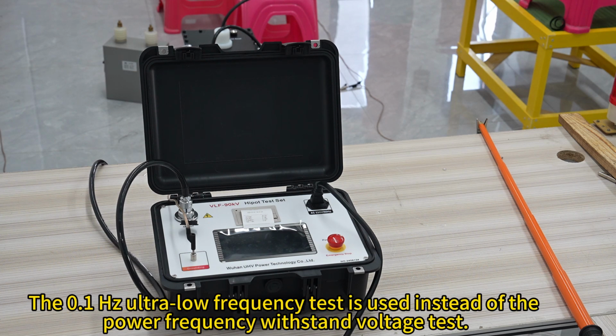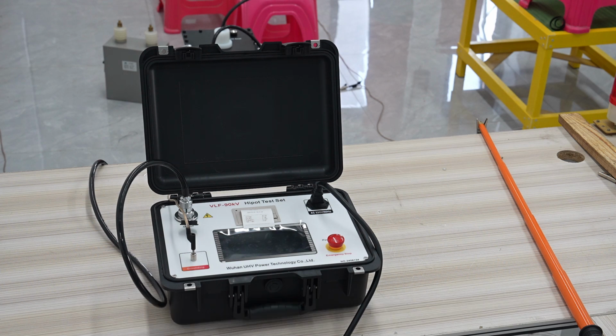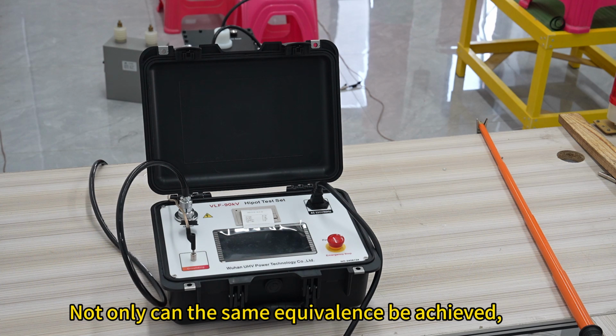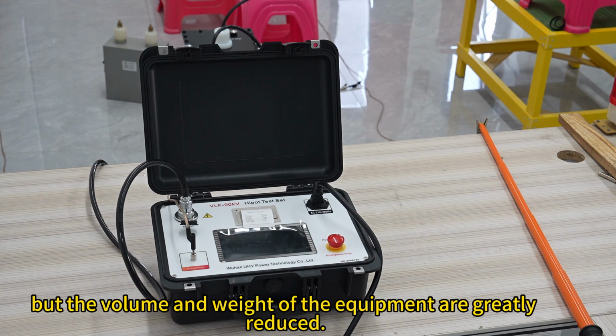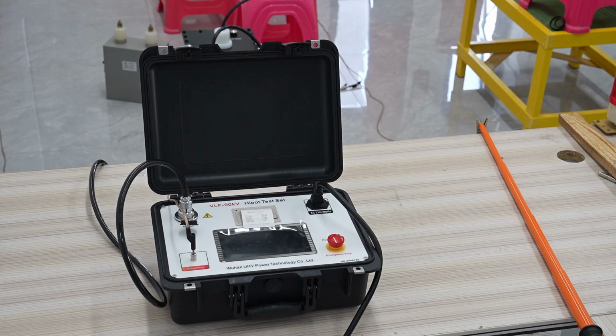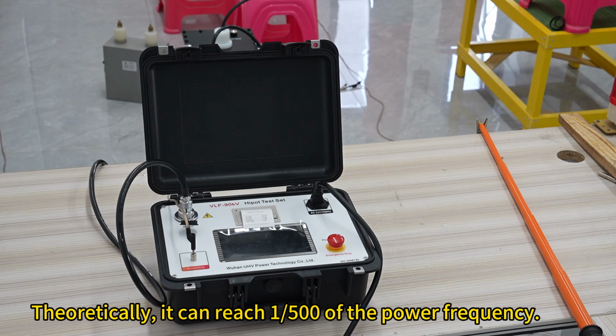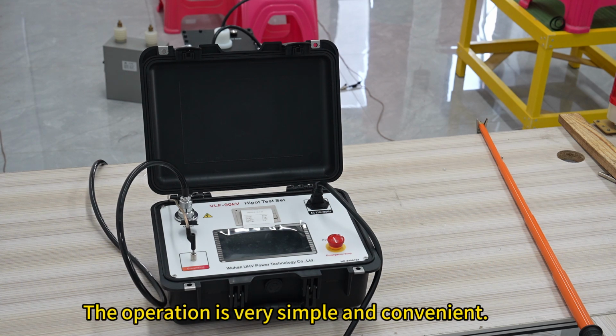The 0.1 Hz ultra-low frequency test is used instead of the power frequency withstand voltage test. Not only can the same equivalence be achieved, but the volume and weight of the equipment are greatly reduced. Theoretically, it can reach 1/500 of the power frequency. The operation is very simple and convenient.